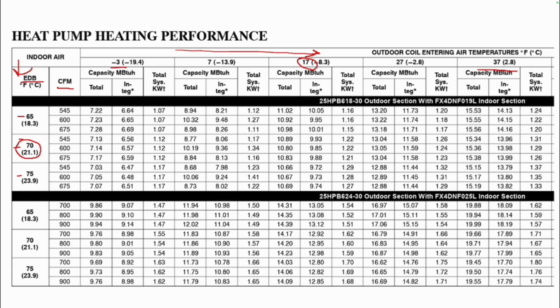Then we still have another selection to look at. Vertically beside that we have CFM. Carrier gives you three choices: 545 CFM, 600 CFM, or 675 CFM. Let's say 600. So how would I use this chart? I'm going to carry 600 over until I get to that 17 degrees. And the capacity of that system as it's running is 10.80, which would be 10,800. Again, this is MBTUH.